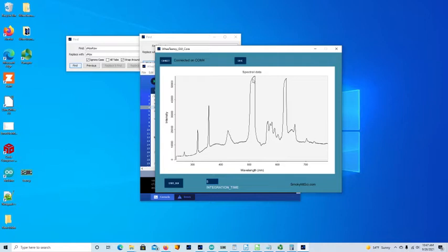So when you see flattened out peaks like this one and this one over here, that means you're not getting real data. That data that you're recording is not particularly real, and that has implications for the width of the lines and other things as well. So it's best to get your really sharp data points or sharp lines and have a lower intensity number.